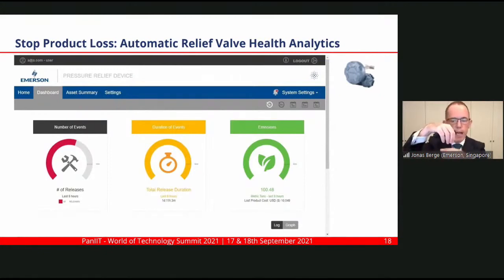But even if the relief valve is not releasing, it may have seeped back after a release and not be shutting tightly. There's a small leak at the seat, but that small leak over time - weeks, months, years - causes great losses. You're able to detect this as well, so you can send that relief valve for overhaul to stop product losses.